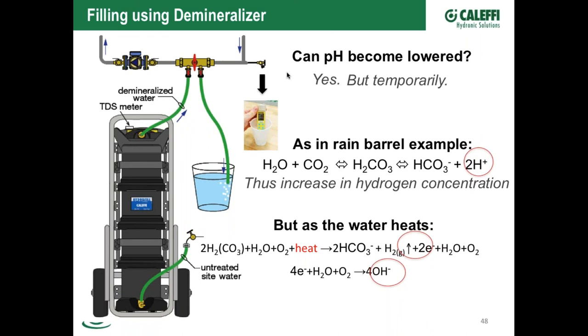The answer to that question is, in both cases—when water is pulled from your municipal supply or ground with a pH of 5, which isn't atypical especially in mountain areas—that by itself is a problem for sure in an open system with low pH. If you collect reclaimed rainwater, say in a rain barrel, it will also have a pH somewhere around 5.5, just like the raindrops themselves. If you had a pH of 5 or 5.5 in a closed hydronic system for any sustained length of time, that's pretty aggressive and would cause problems not only on your stainless steel heat exchanger, but first on weaker metals like irons, steels, and coppers, before stainless steel. So stainless is the least of your concerns.